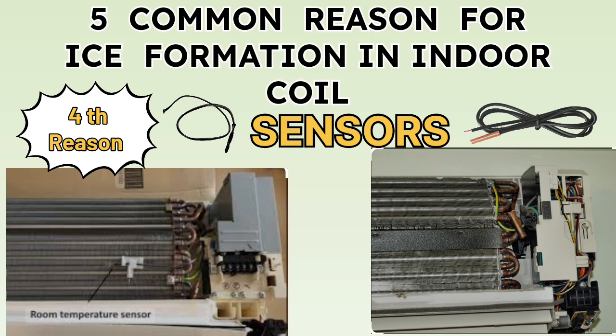Reason number four: when you see ice formation in your indoor unit, you have to check the sensor. Sometimes our coil sensor or room sensor doesn't connect properly to the auto unit, and at that time also there is ice formation. If you get a sensor error, check the coil sensor and room sensor and you will get the solution for the ice formation in your indoor unit.